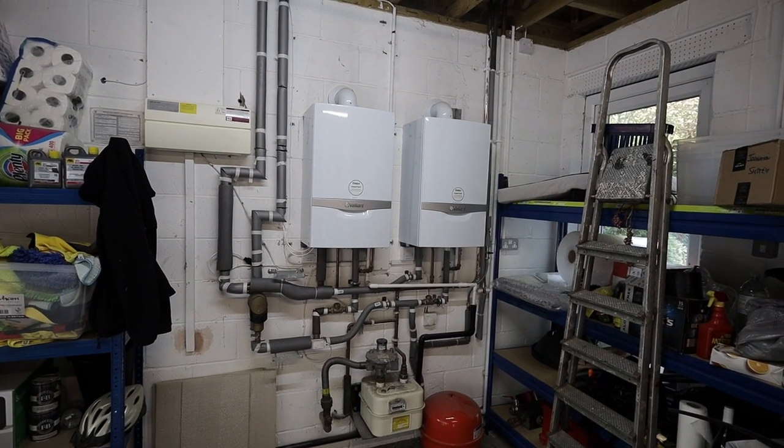It could have been done on Vaillant controls, but so many zones would require VR92 units at around £160 each — we'd need at least 10 of them plus VR70 extensions, and the cost was just prohibitive. The owners wanted influence over which parts of the house are heated, so I had to keep it on third-party controls. If there is no follow-up video on this job, that means the project failed. If it is successful, I will post a follow-up video next year where we compare energy use from the previous year and discuss how the system performs. Thanks for watching and I'll see you soon.